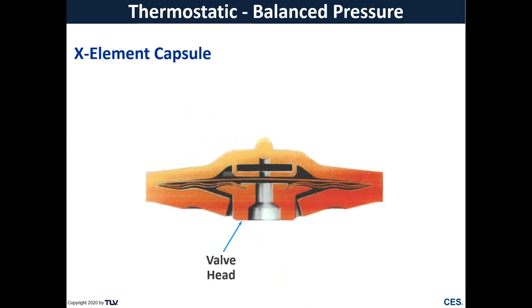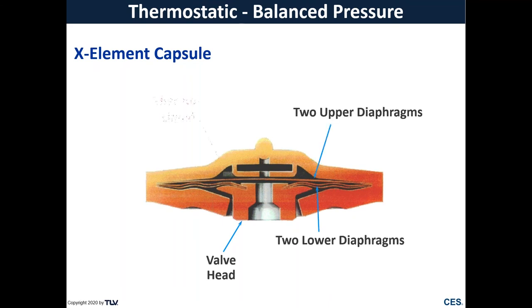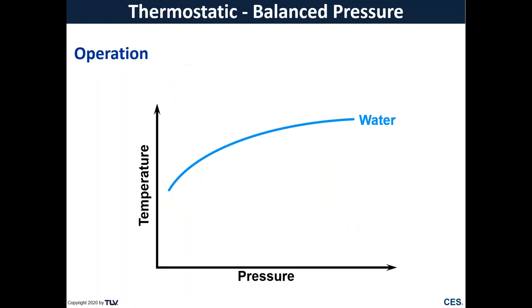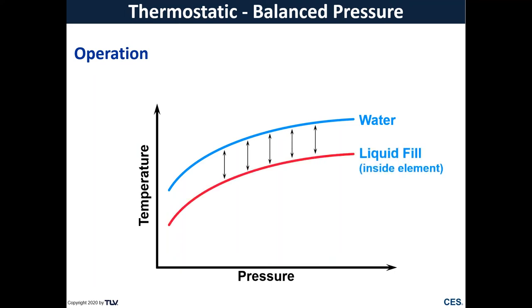So we have a valve head attached to two lower diaphragms and then two upper diaphragms that encase a thermal liquid. This thermal liquid is a mixture of alcohol and water. I'm sure many of you are familiar with the saturation curve of water. As you increase pressure, you also increase the boiling temperature of the water. Well, by having an alcohol water mixture, we can have a boiling point curve that's a certain degree lower than that of water. And so the goal here is to maintain a boiling point less than water at any given pressure.